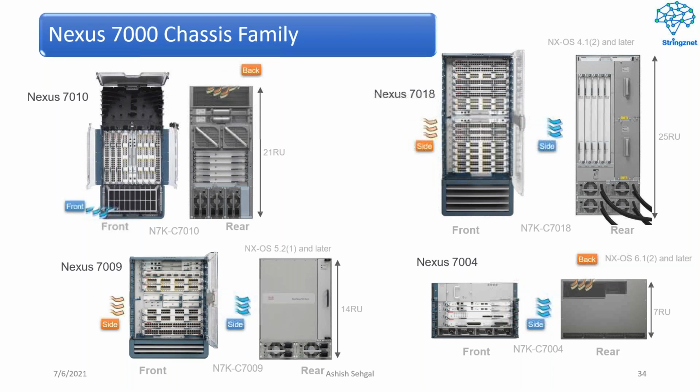Glass doors are definitely removable. Cisco has provided this flexibility, and no one in the data center with Nexus 7000 switches is fixing these glass doors. Everywhere you go, you will see that the glass doors are removed, because they are supposed to choke the performance of the line cards. It's being experienced.